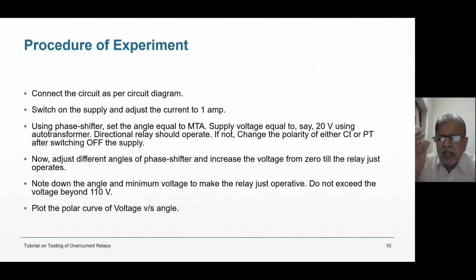Because relay operation is seen by naked eye, or some say in static relay, there will be some LED which will light, right? In numerical relay also there will be some LED which will light. And also it will say relay operated on the display panel. There will be something, so you will be able to know that the relay is operated. Note down that voltage at which relay is just operated. So go on changing the angles and find out the minimum voltage. Try to see that you do not exceed 110 volts because relay will be damaged.